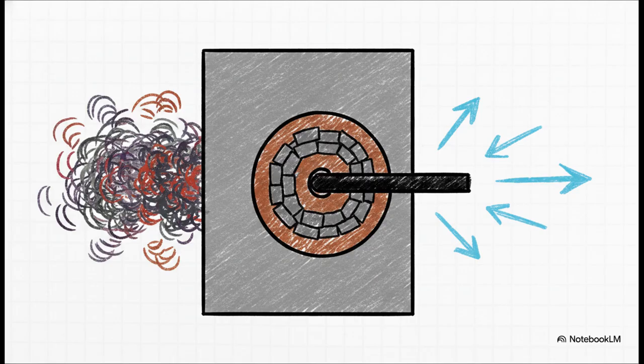This totally stops a terrifying effect called pressure piling, where an explosion travels down a pipe, compresses the unburnt gas ahead of it, and triggers an even more massive secondary explosion. And finally, maintaining a static overpressure in safe areas ensures that if there is a leak, clean air pushes out, so the hazardous gas can't push in.